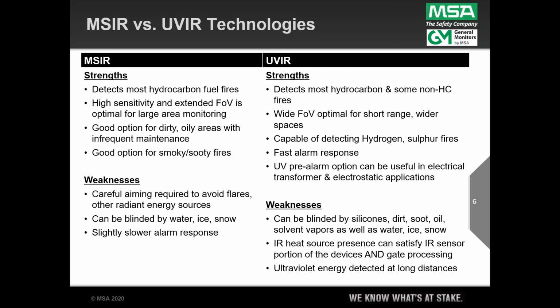It's also a good option where the area is dirty and oily and just may not get cleaned as well. And that translates also to a good option for sooty and smoky fires, because those IR detectors actually have a higher resistance to optical blinding than a UV sensor does, but they're not impervious. And now on the weaknesses side of this, because that extra sensitivity is out there, you have to be careful in the aiming of it. And if there's a flare stack, a heater, a boiler or a reactor with a combustion process going on, the reality is you have to be careful in your aiming practice.